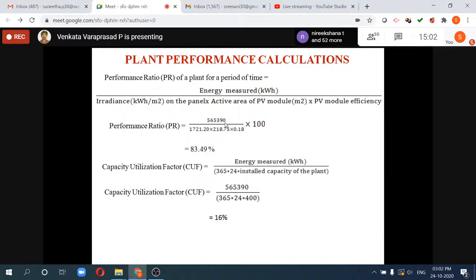5,65,390. So in the denominator, we will multiply the irradiation value, the active area of the PV modules, and the PV module efficiency, that is 18%. By considering these values, you can find the plant performance and the plant utilization factor.